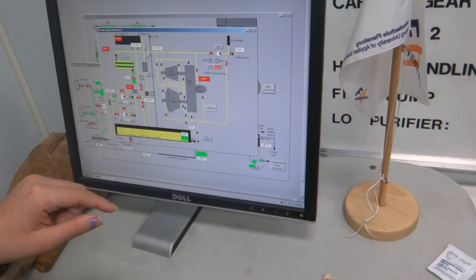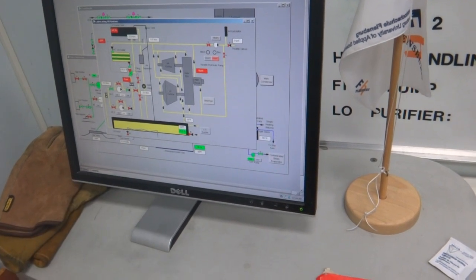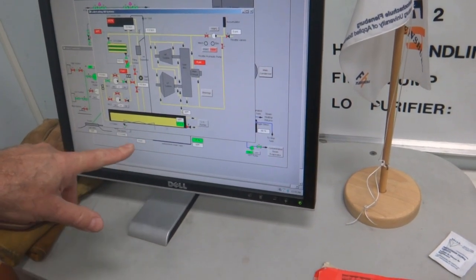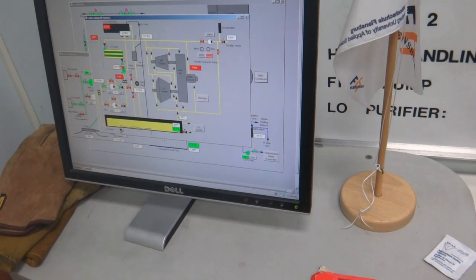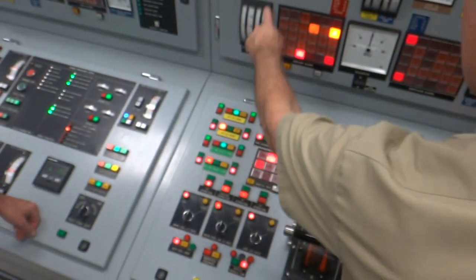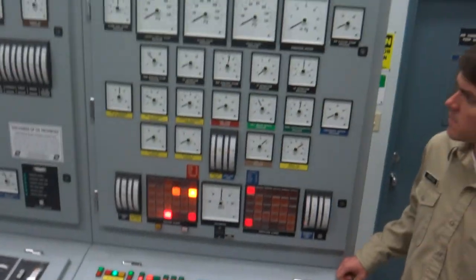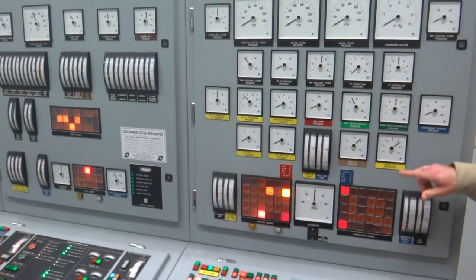What about the bottom one? To start heating up. Oh yeah, heat up the sump, because it's 68 degrees, we need 110 to be running. And start the lube oil pump. Yeah, this is open. Start the lube oil pump, and you'll see lube oil pressure coming up. So now we got lube oil on.